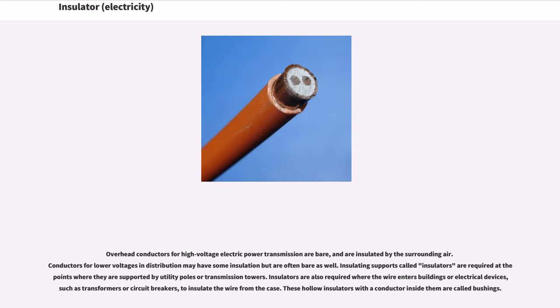Overhead conductors for high-voltage electric power transmission are bare and are insulated by the surrounding air. Conductors for lower voltages may have some insulation but are often bare as well. Insulating supports called insulators are required at the points where they are supported by utility poles or transmission towers. Insulators are also required where the wire enters buildings or electrical devices, such as transformers or circuit breakers. These hollow insulators with a conductor inside them are called bushings.